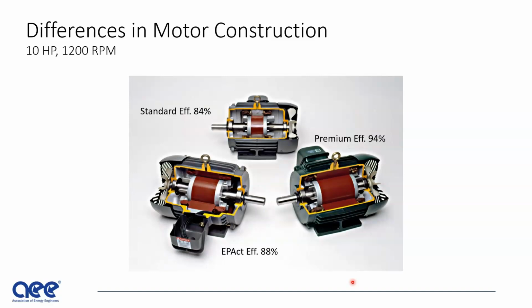Here you can see an example of a 10 horsepower motor designed with the different efficiencies. What makes a motor more efficient is the additional material. These are the same 10 horsepower, but you notice that when you move from standard through EPAct through premium, the stator gets much bigger and the rotor gets much bigger. You have much more material. So not only are you reducing the electrical resistance, you're also reducing the magnetic equivalent of electrical resistance, which is magnetic reluctance.